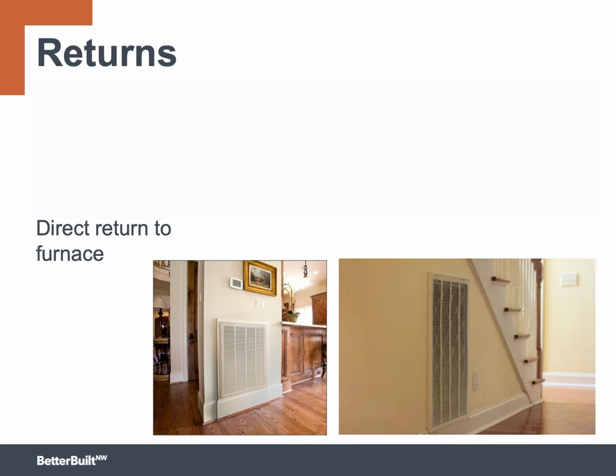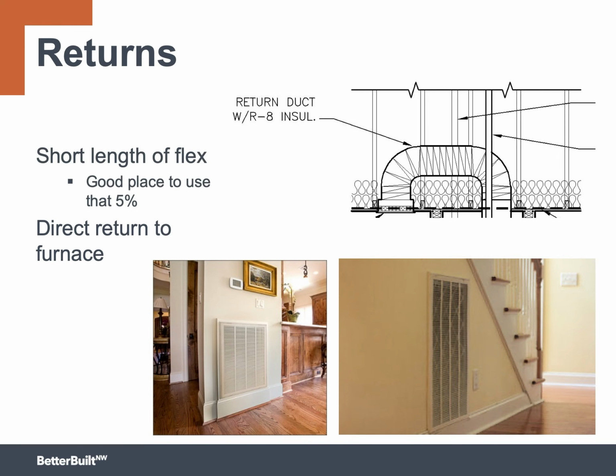A direct return is an option, but it does tend to be a noisy one, and many builders would not accept the look. Most people that have tried the ducts inside approach are using a very short section of flex. Many times it runs through the attic space. Because it's insulated flex, it absorbs some of the sound. This is really a good place to use that 5% exception that you have. That's the 5% of the duct length that is allowed to run outside the thermal boundary.